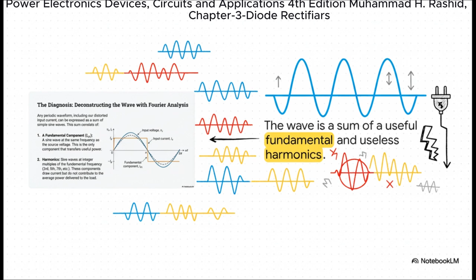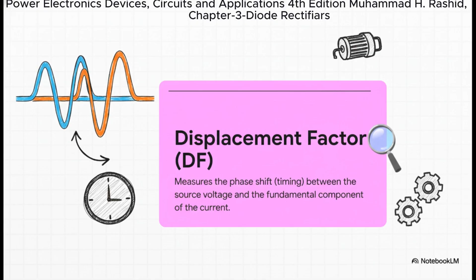First up, we have the displacement factor. This is probably the classic power factor you learned about in your first circuits class. It only looks at the timing difference, the phase shift, between the voltage and that one useful fundamental part of the current. It's all about when the current is drawn, not what shape it's in.